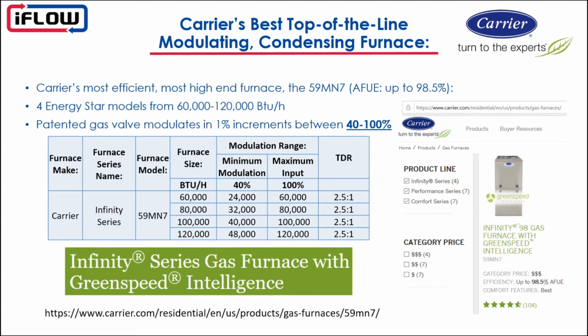But let's look at some of the newest product in the market to see if that may help us with some of these issues. So what we're looking at here is the newest Carrier product, the 59MN7. It has an AFUE of 98.5, so it's the highest Carrier furnace in terms of AFUE. It's an Energy Star rated product. It has 4 models, 60, 80, 100, and 120,000 BTU. And one of the key features of this unit is that it increments in 1% increments between 40 and 100%.